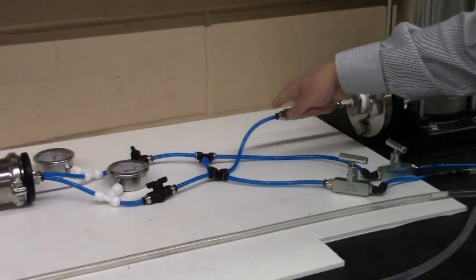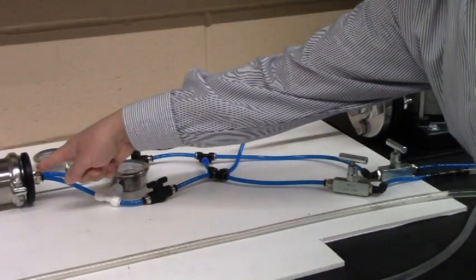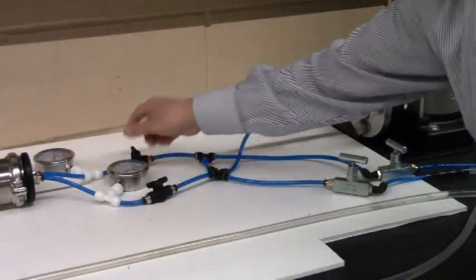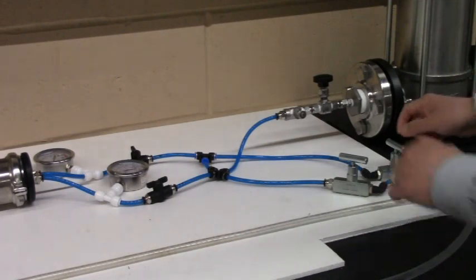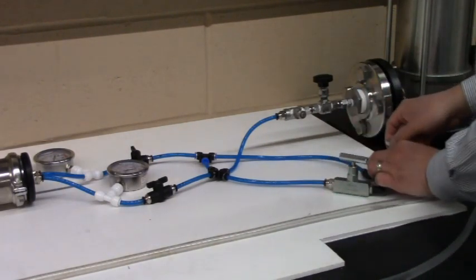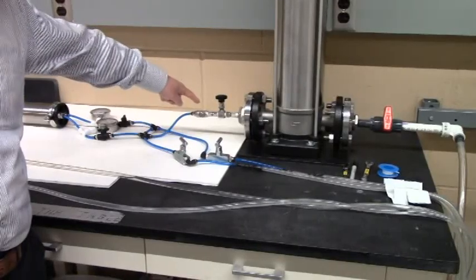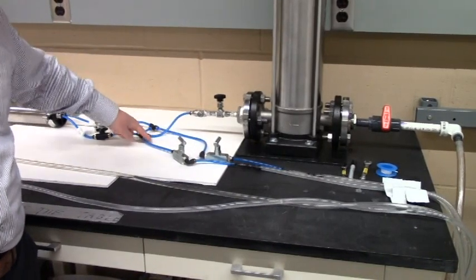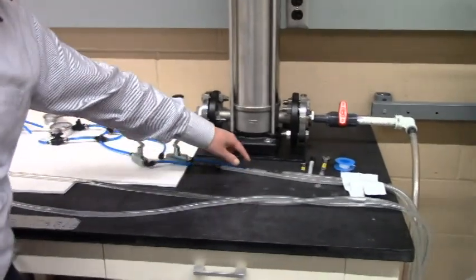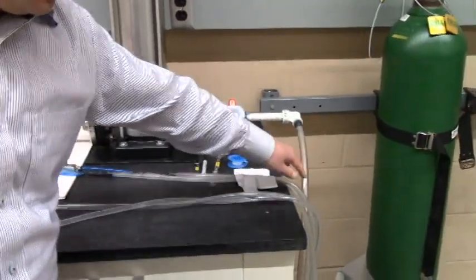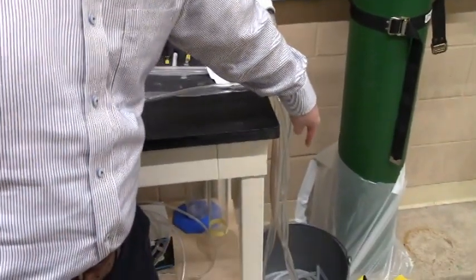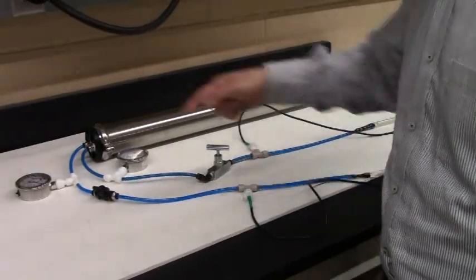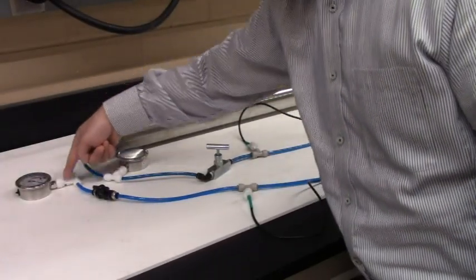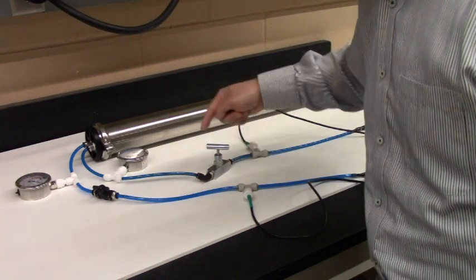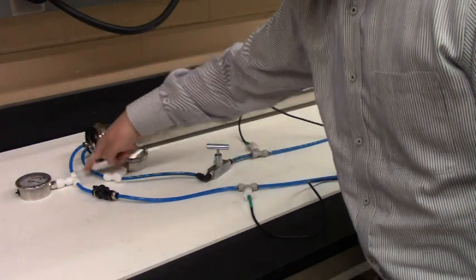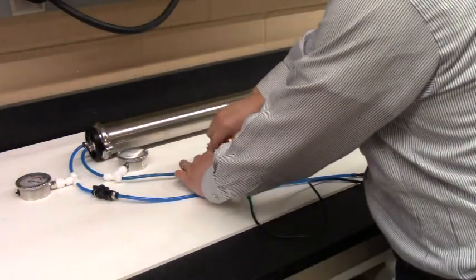Once water is discharged from the pump, it normally goes to the filter inlet if the back flush inlet and the bypass valves are closed. If the bypass valves are open, then water can be diverted to the bypass lines instead of going to the filter. On the back end of the filter, water can either flow to the filtrate line or reject line, more or less.